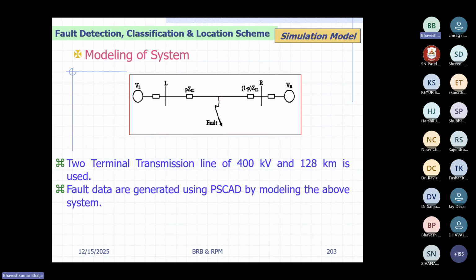So the thing is that you have to vary the location of the fault. That is one variable. The second variable is the type of fault. All 10 types of faults you can simulate and generate the data. Let's say you have considered, for example, 128 kilometers, so a total of 30 different locations varying from 0 to 128 kilometers. So 30 is your fault location variable. Then fault type, 10 types of fault, that is fixed: three line to ground, three line to line, three double line to ground, and one triple line to ground. So 10 types. So 30 locations into 10, so 300.